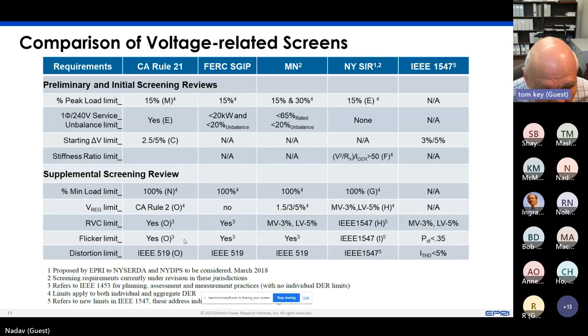Go ahead, Nadav. I think we can move on. I think this is a good summary of motivations to improve the process. The utilities have a lot of motivations, and obviously developers and customers do too. But you can see just trying to apply what's in the standards, especially with inverter connections, and then with the increasing numbers, not having extra staff to look at these systems, the idea that there's a kind of a hosting capacity limit and maybe ways to use that in both planning and interconnection decisions. As I mentioned, protection issues, or the complexity that having energy storage brings, where it could be generating, it could be storing, and the rapidity that it can do that is not really limited unless it's built into the system to limit charging and discharging.